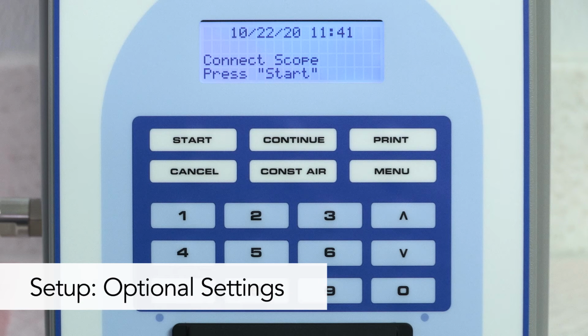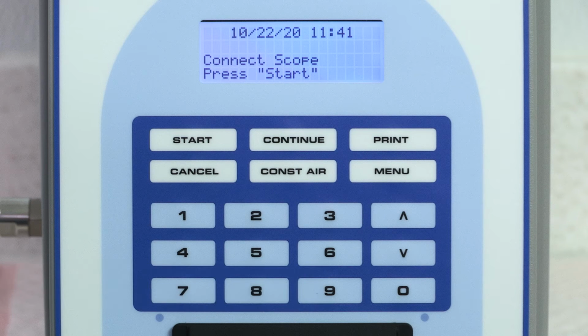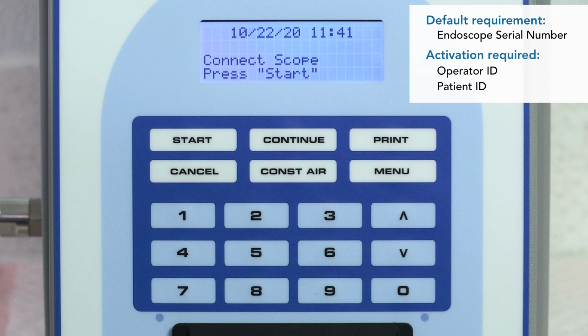Next, we'll walk through activating data prompts. Effective data management begins with the operator entering identifying data at the beginning of a leak test. While an endoscope serial number must always be entered at the beginning of a leak test, the user must activate the operator ID and patient ID prompts in advance if this data is to be collected during the leak test.